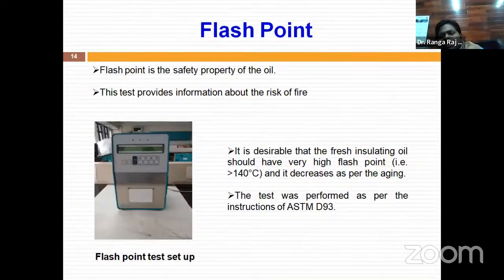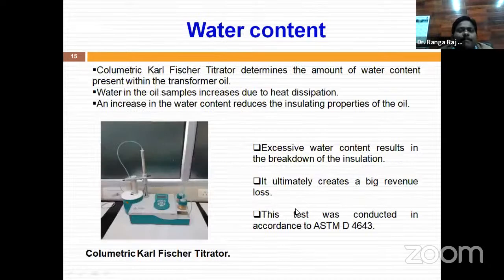Next test is flash point. This is also one of the important tests. Flash point is the safety property of the oil, and this test provides information about the risk of fires. If we subject the oil beyond a certain temperature, we find flashes, which are very dangerous. So we should know the maximum allowable temperature, and that comes from this flash point test. The relevant standard is ASTM D93.